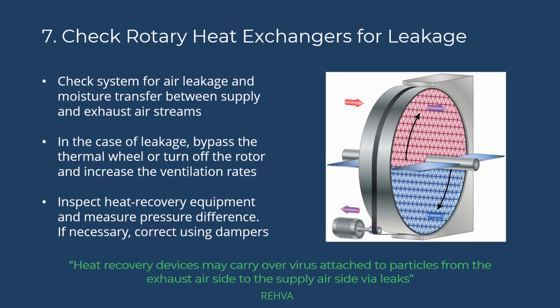Inspect your system for air leakage and, if it is found, CIBSE recommends bypassing the thermal wheel. If the wheel can't be bypassed, the rotor should be turned off and the ventilation rates increased. In addition, heat recovery equipment should be regularly inspected and the pressure difference measured.